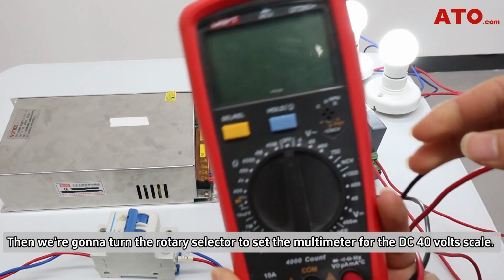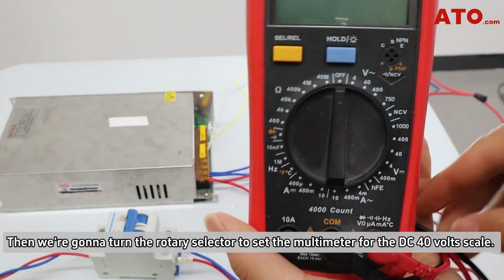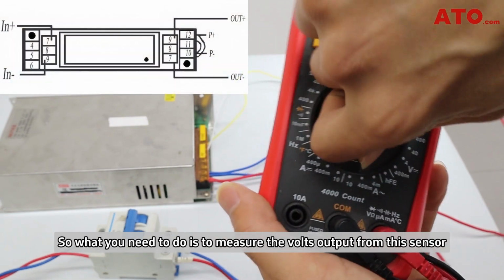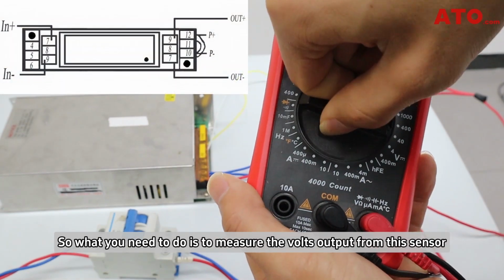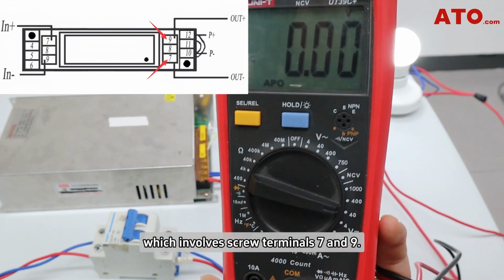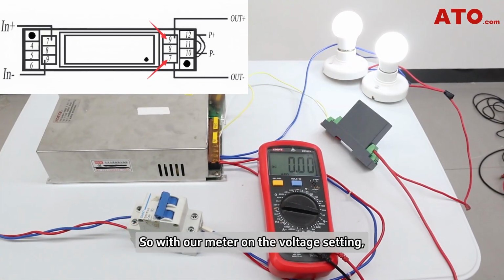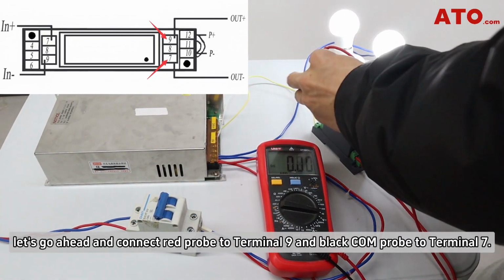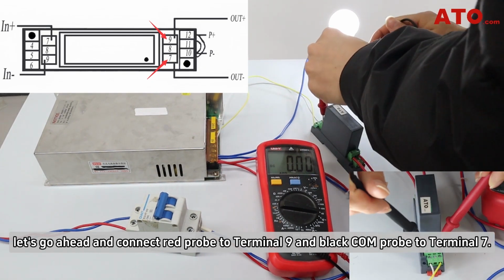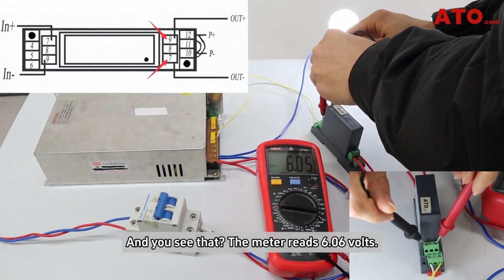Then we're going to turn the rotary selector to set the multimeter for the DC 40 volts scale. What you need to do is measure the voltage output from this sensor, which involves screw terminals 7 and 9. So with our meter on the voltage setting, let's connect the red probe to terminal 9 and the black common probe to terminal 7. And you see that the meter reads 6.06 volts.